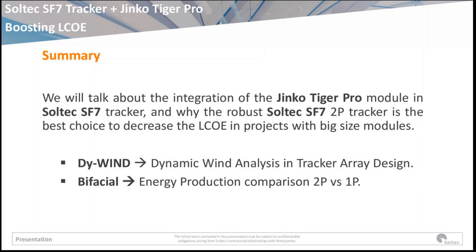To do so, we will go through two main topics. The first one is the Dy-WIND methodology we at Soltec use to calculate the structural analysis of the tracker. It is a dynamic wind analysis in tracker design. As I said, it's a structural calculation methodology developed by Soltec with the support of RWDI during the last few years. It allows us to predict the behavior of the tracker against the wind when using PV modules with large sizes, as we are talking about today. And the second topic I'm going to go through is bifacial technology and how to make the most of bifacial using Soltec trackers combined with the Tiger Pro module. So let's go.